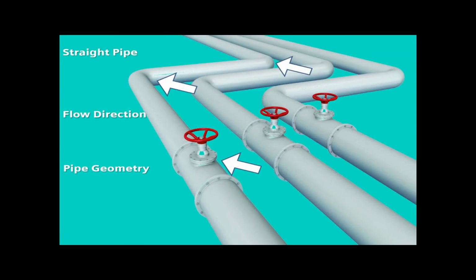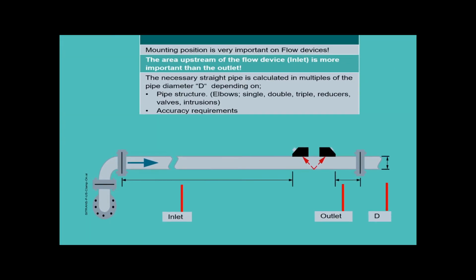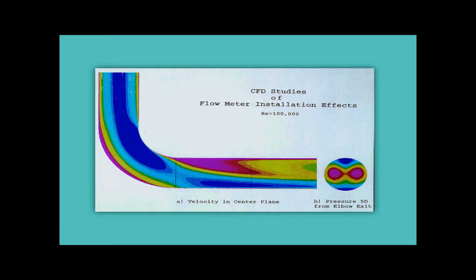In deference to an old TV ad, it's what's up front that counts. Multiple elbows, particularly if they are out of plane, will create swirl conditions that persist much more than 10 diameters. A condition that is also affected by the fluid's viscosity. These effects were documented in studies performed by the NIST and will impact any area averaging flow meter.